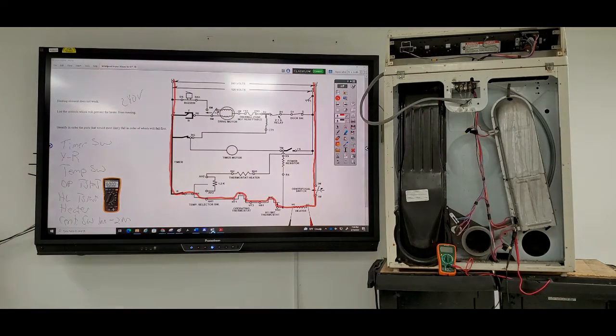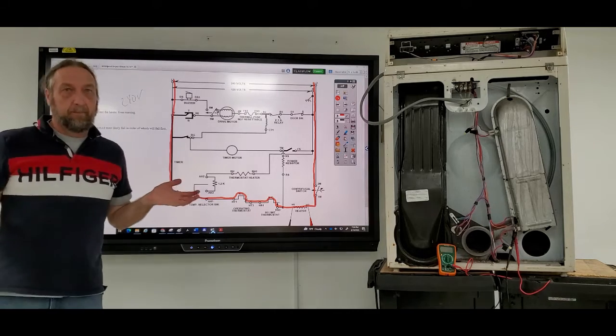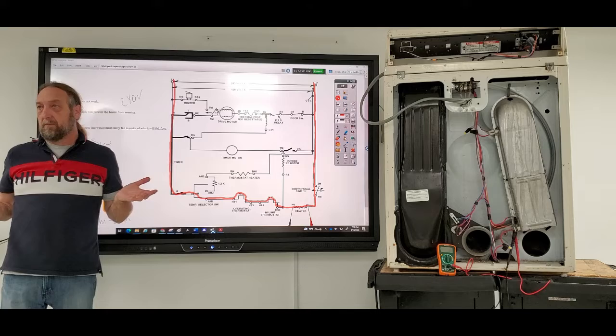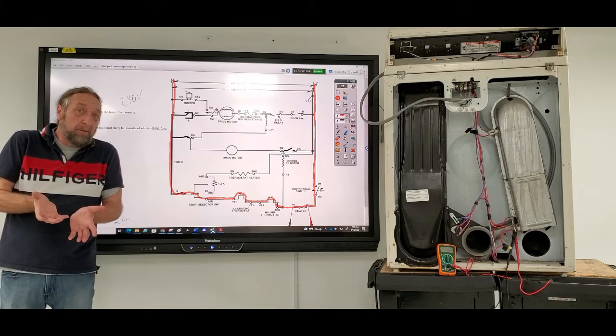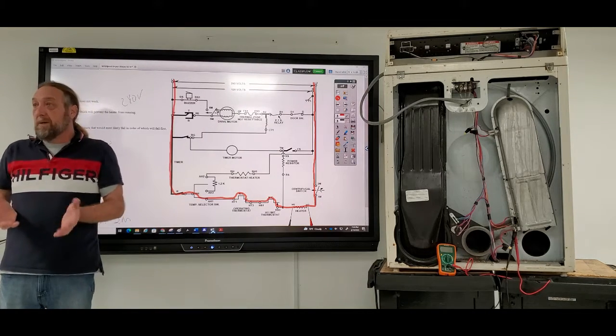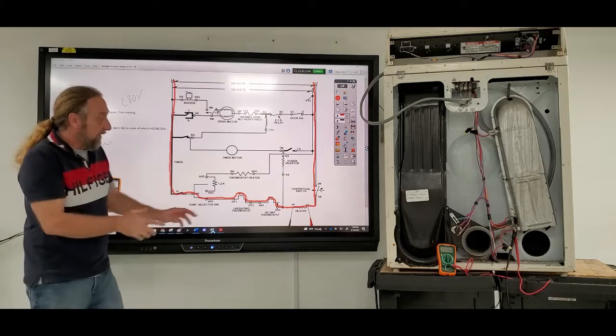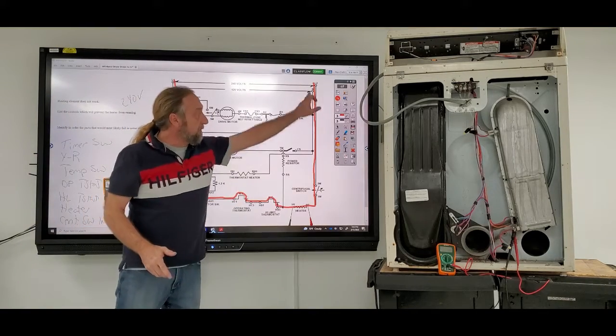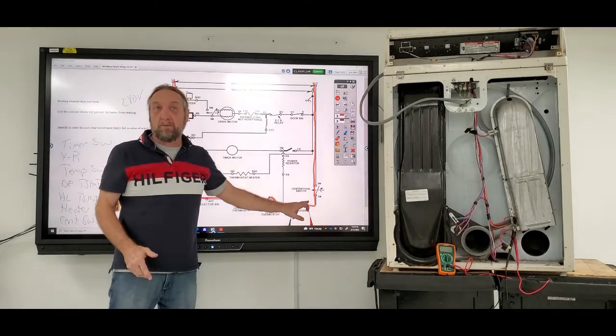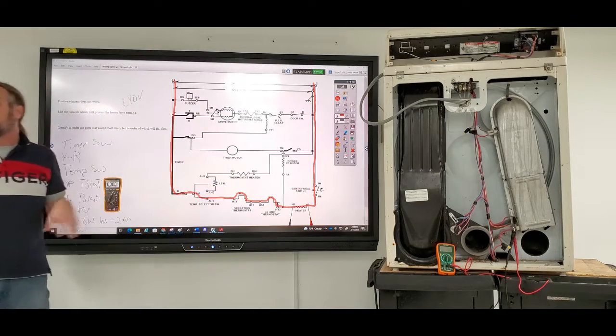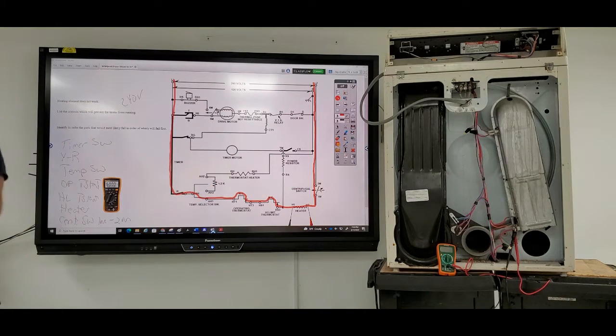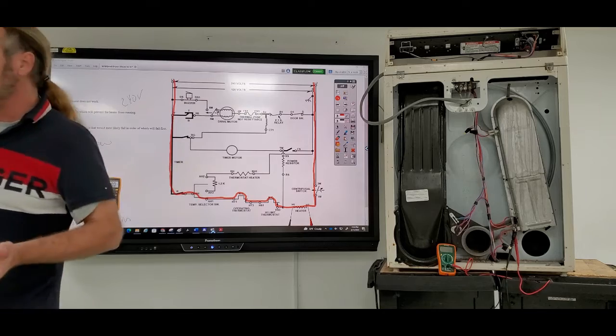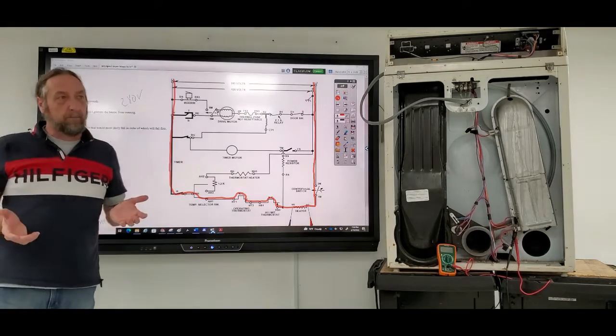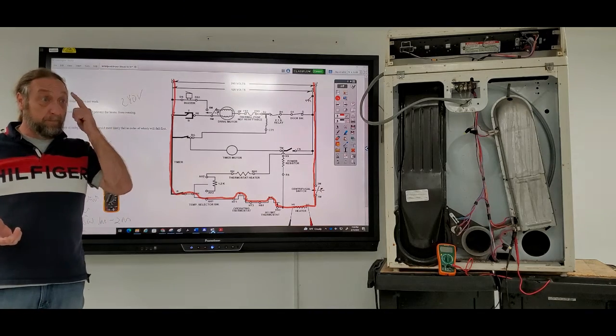Because if I have 240 there, what's my problem? The heater's bad. Do I need to ohm it out? Not really. No. Because there's nothing left. If I have 240 there, that means my centrifugal switch is closing. And it means all these thermostats and timer switch and everything else are closing, because I wouldn't have 240 if any one of those parts failed. So in the competition, we would put heater failed open.